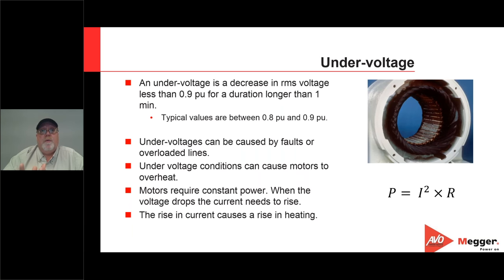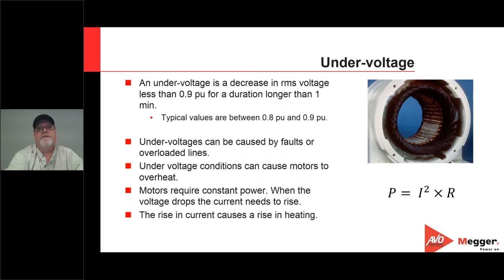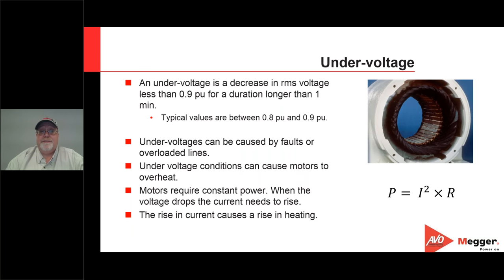What can under voltages cause? One of the key issues is with motors. A motor has to supply constant power, so when the voltage goes low, the current has to increase to maintain that power. As the current increases, your heating effects increase — power equals I squared times R. So as the current goes up, heating effects go up. Under voltages can also be caused by overloaded lines as well as large loads that are turned on.